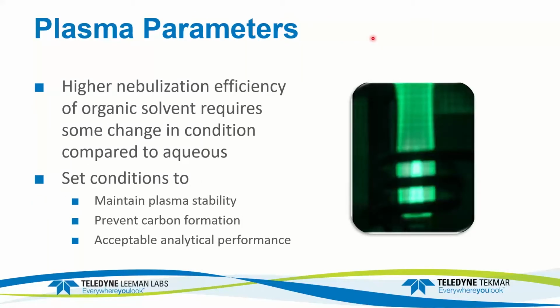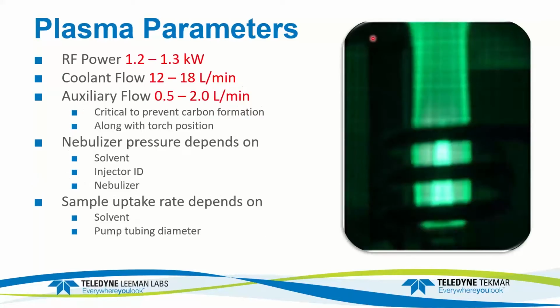Plasma parameters. Because of the higher nebulization efficiency you get with solvents, you have to change the conditions a little bit compared to what you do for aqueous analysis. So in this case, you're going to set the conditions. You want to maintain plasma stability. You want to prevent carbon formation, which is dependent on position and gas flow. And you want to be able to maintain acceptable performance. So for the plasma parameters, they typically will be somewhere within this range.